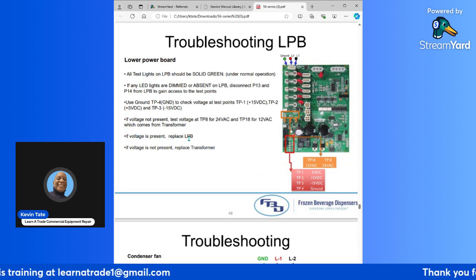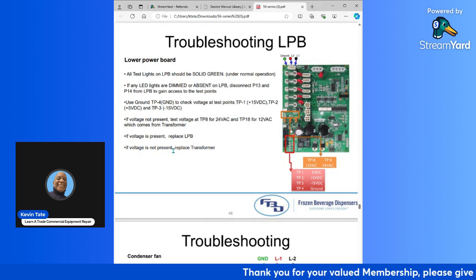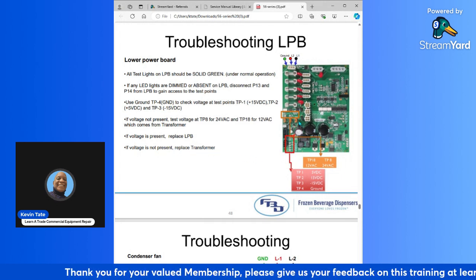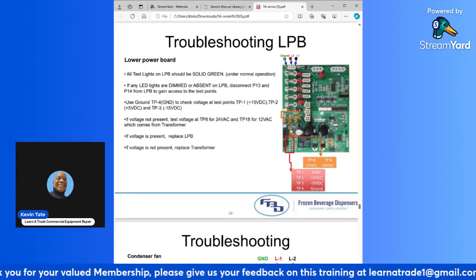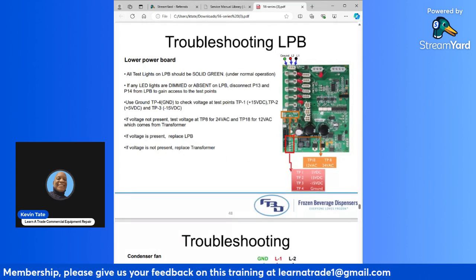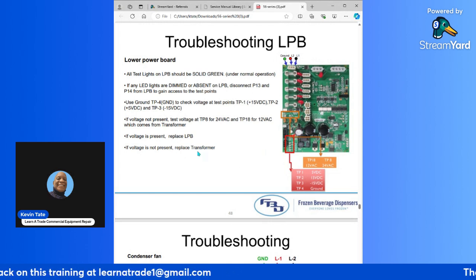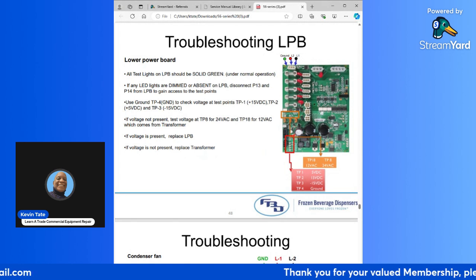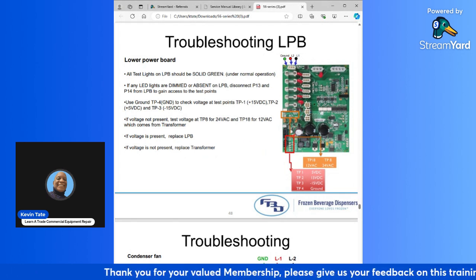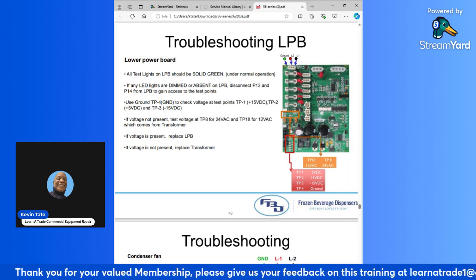If voltage is present, replace the lower power board. If voltage is not present, replace the transformer. So if you test those points and you have no power, you would then replace the transformer. There's an issue with the transformer. And that's that small transformer that sits down below, and the lower power board is right to the right-hand side of that transformer.